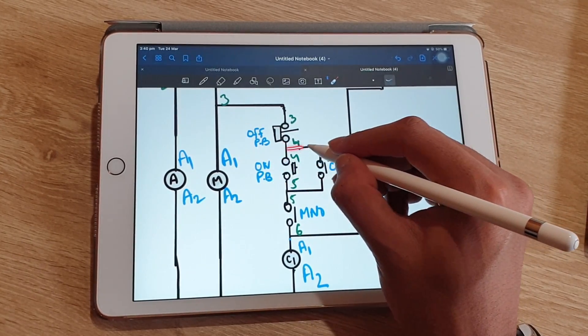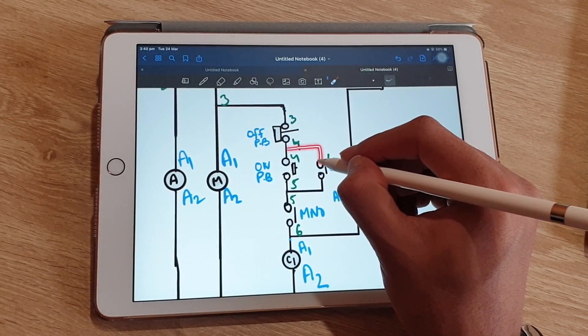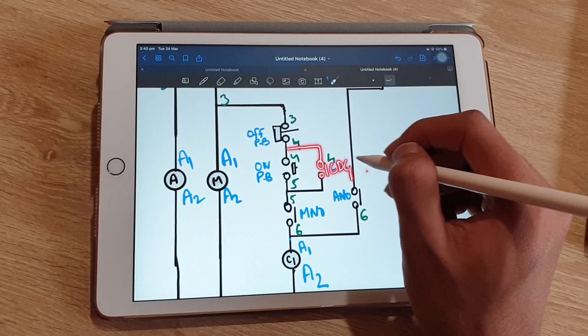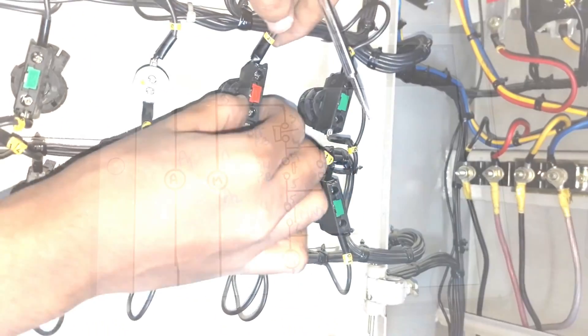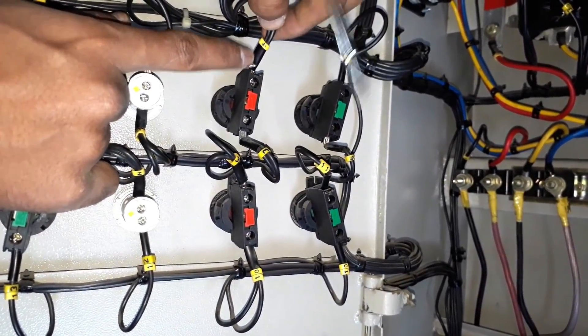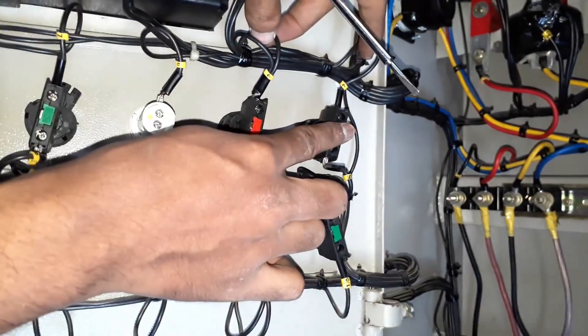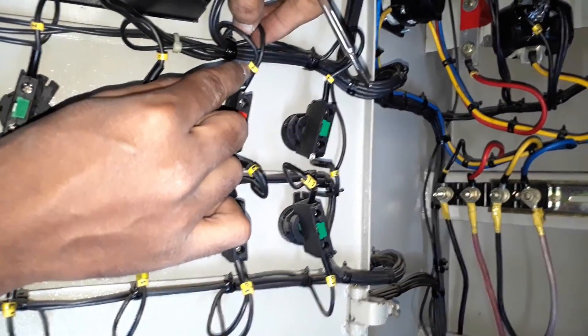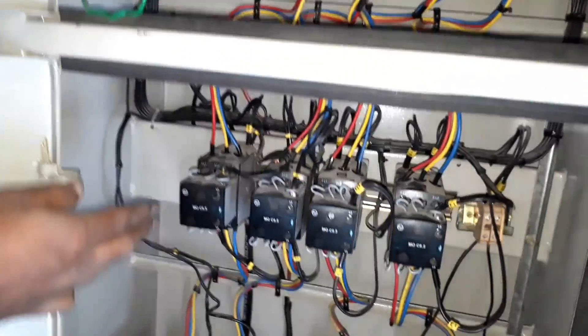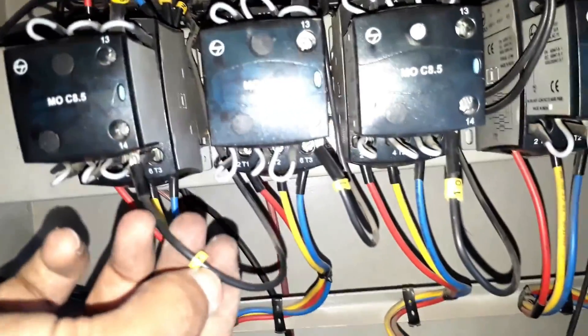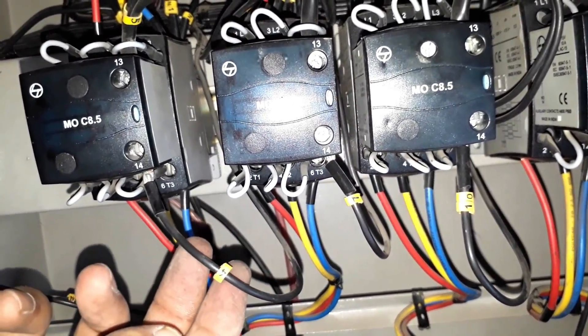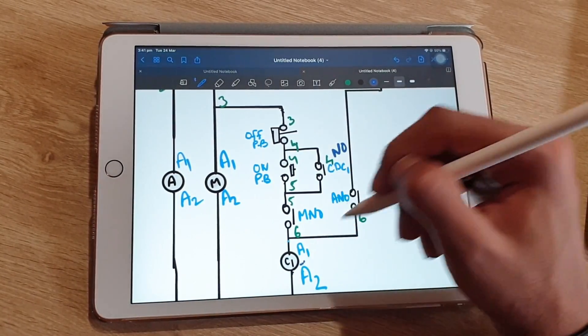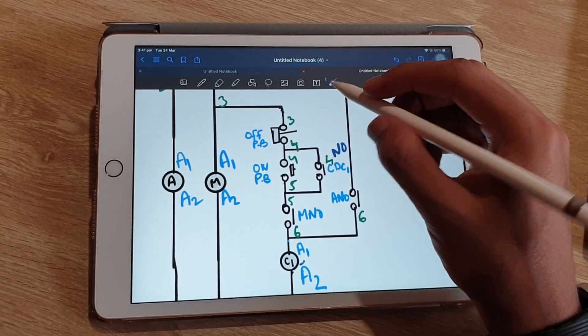The second wire from terminal number four is connected to the NO of CDC1, the capacitor duty contactor. Showing you practically: two wires are taken out from the off push button tagged as four — one wire is connected to the on push button as shown in the circuit diagram, and another wire is connected to the NO of the capacitor duty contactor. This is contactor C1 and the NO of this contactor is the CDC1.